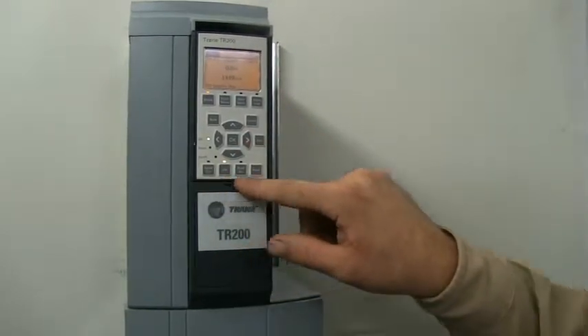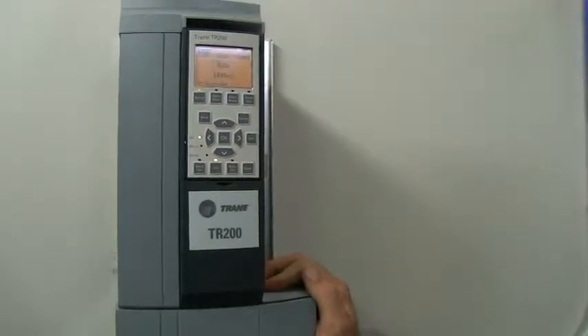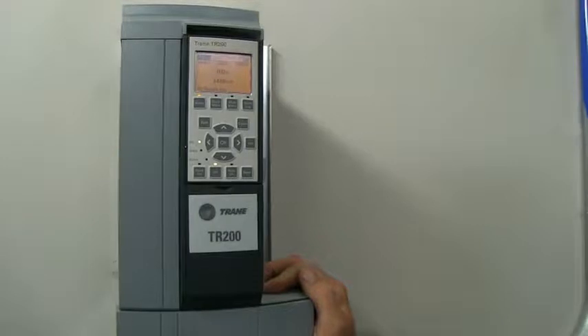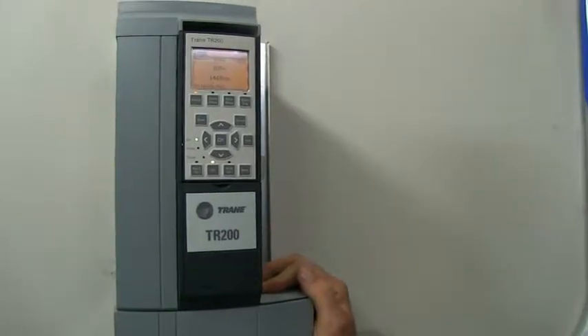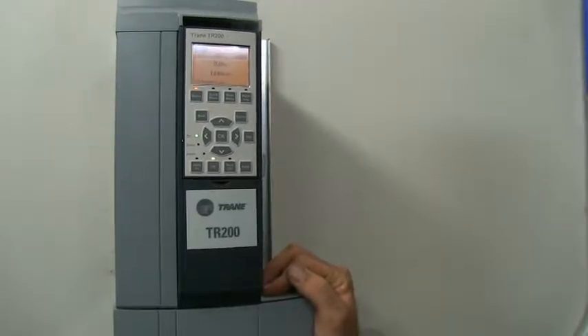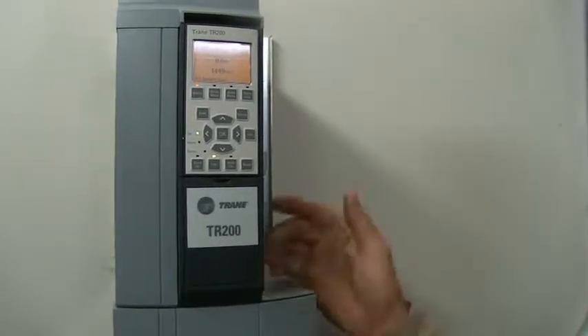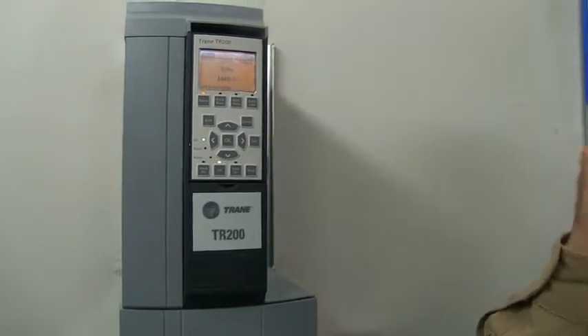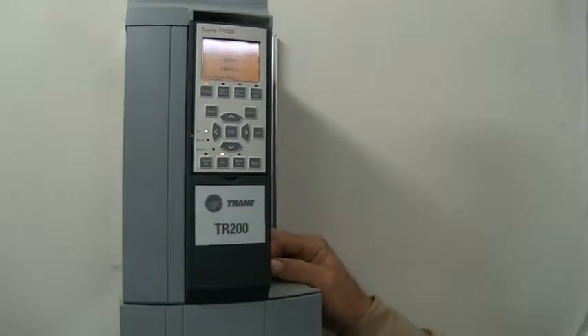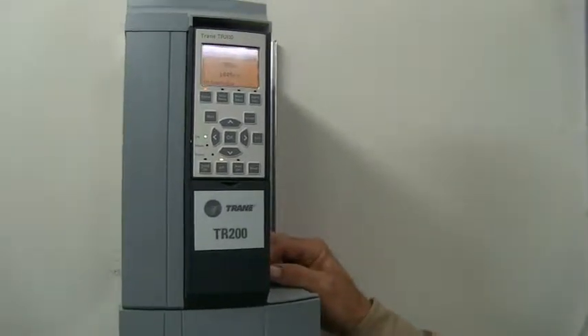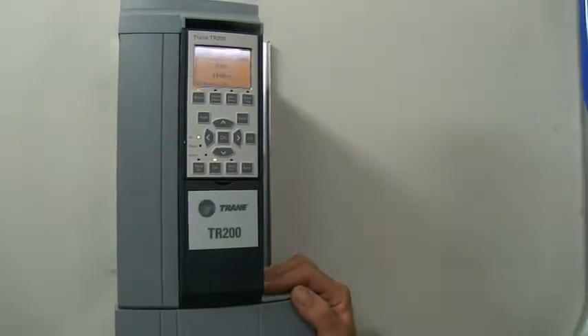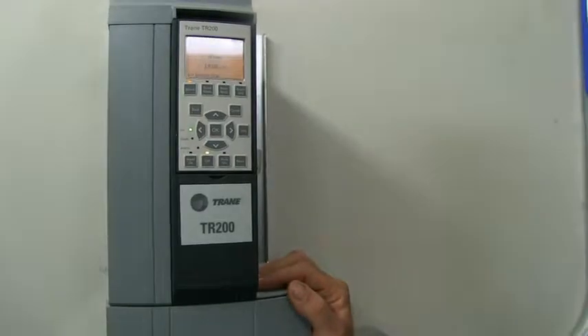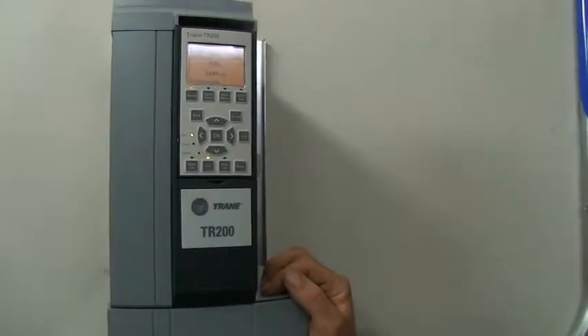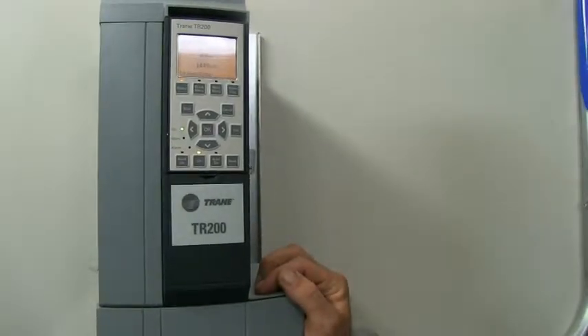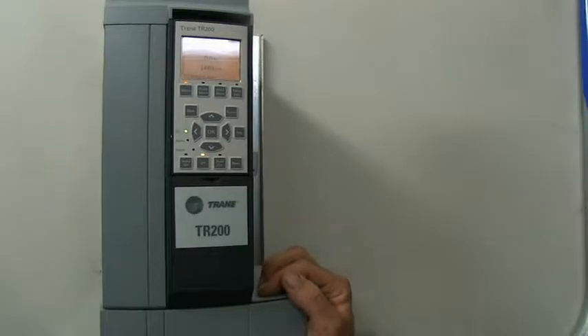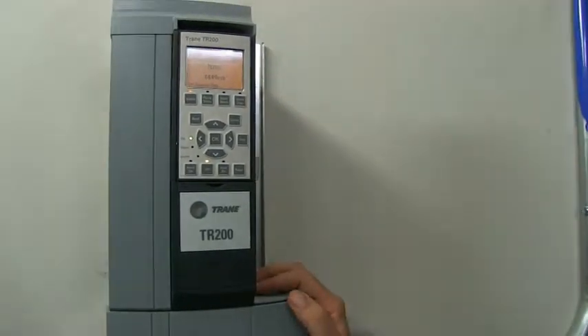Let's see, the bottom set of buttons. The hand button, that's how you operate the machine through the VFD, where you can set your own desired hertz setting. The next button is the off button, of course, that shuts the air handler down. The button next to it is the auto button. When in auto, the drive is controlled through the BAS system. So BAS takes precedence and sets the VFD speed to its desired setting. The last button is the reset button. If the drive happens to have an alarm or fault and the alarm or fault's cleared, you hit the reset button to actually remove the alarm display off the screen.